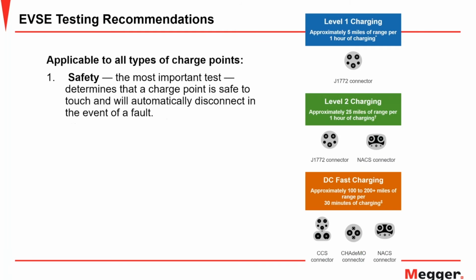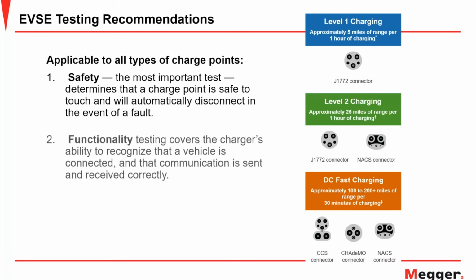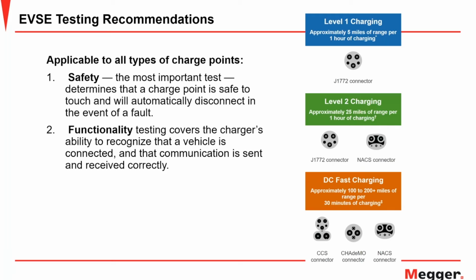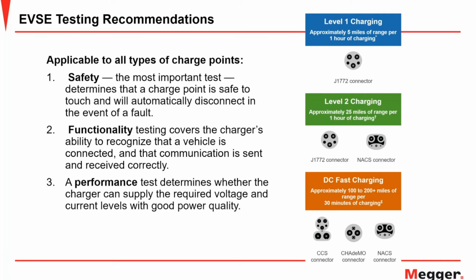Our recommendation is basically three types of testing that need to be done on charge points. The first and most important is safety - is it safe for the person to walk up to it, connect to it, test and charge? The next most important is functionality, which covers the communication protocol and triggering events between the electric vehicle and the charge point itself. And then lastly, performance - how good is it at supplying as much energy as required or expected, and is it supplying that power with adequate, acceptable power quality? There's more to it, I'll dig a little deeper into each one, but those are the three segments we recommend when testing electric vehicle supply equipment, or EVSEs.